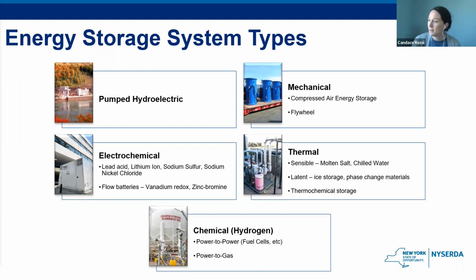Then we also have thermal energy storage. Thermal energy storage looks to capture heat and cold to create energy on demand or offset energy needs. A facility can use off-peak electricity rates, which are lower at night, to produce ice, which can then be incorporated into a building's cooling system to lower demand for energy during the day. And next we have hydrogen energy storage, or chemical, where excess electricity generation can be converted to hydrogen and stored, and eventually re-electrified.